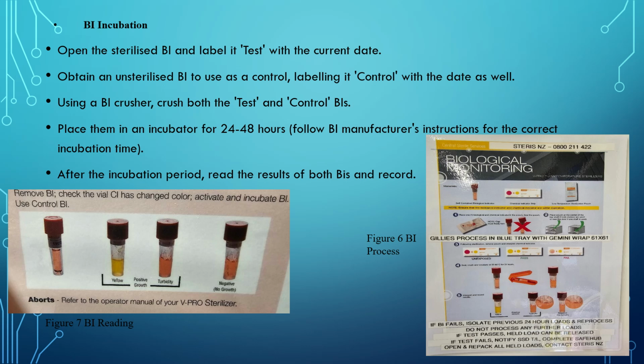The reason why we are testing for 24 hours is that we don't have the 7 minute reading one. If we read the BI within 7 minutes, it would be a faster reaction of the BI changing its color, and if there is bacteria growing, it will tell us within 7 minutes. But this one we are leaving for 24 hours because of the standards and protocol we follow in Southern Cross Hospital, and the examples are shown below.